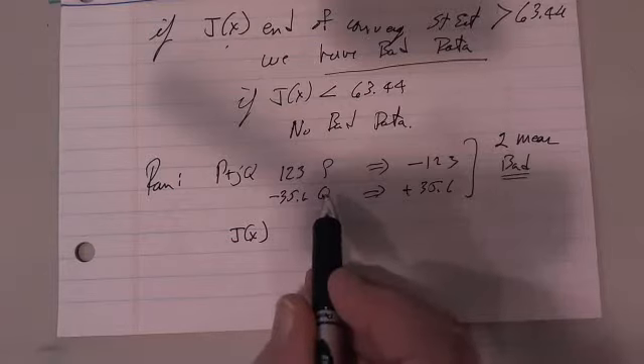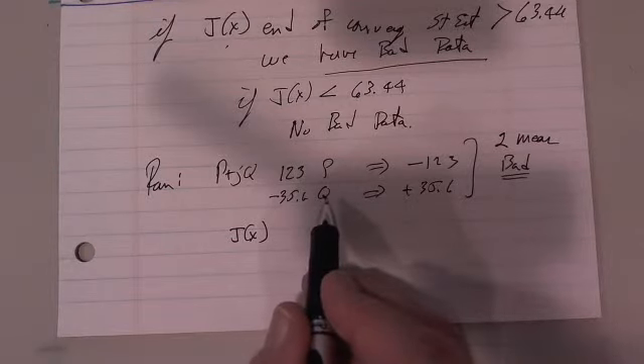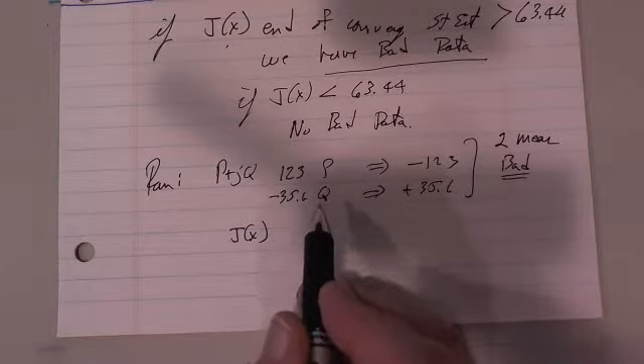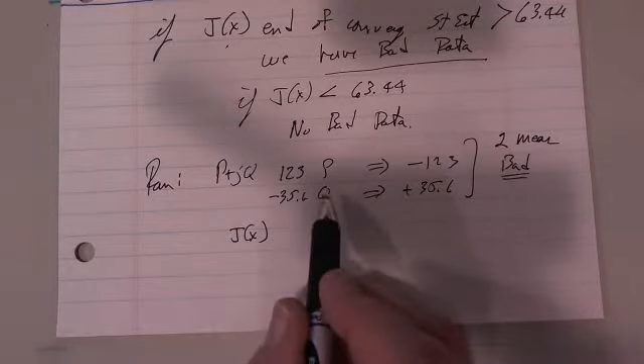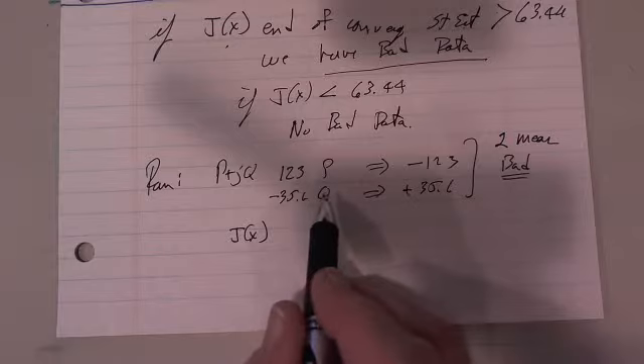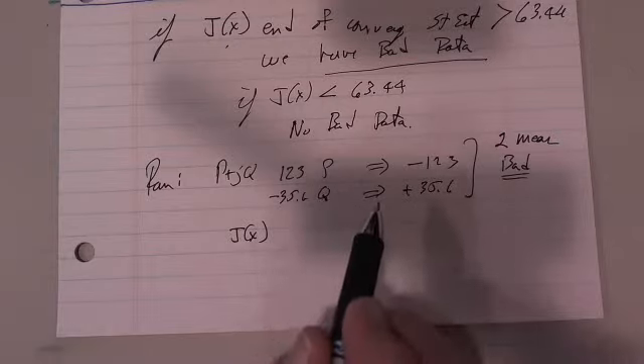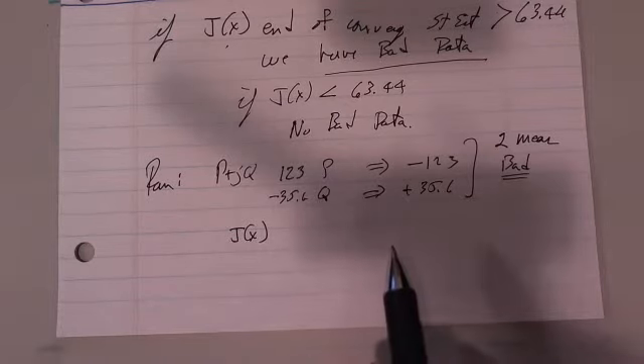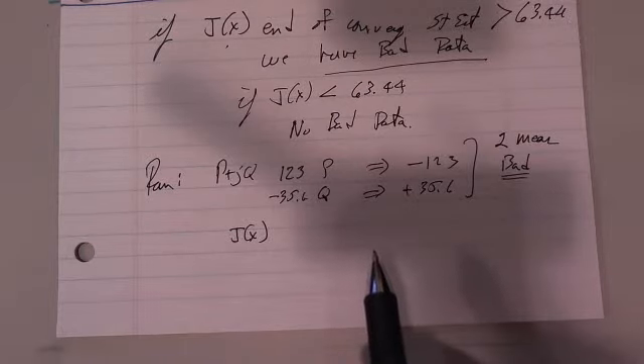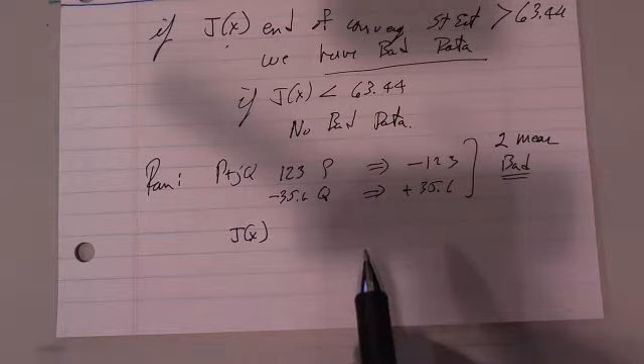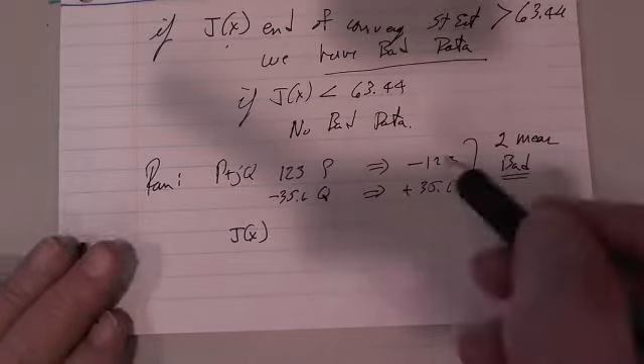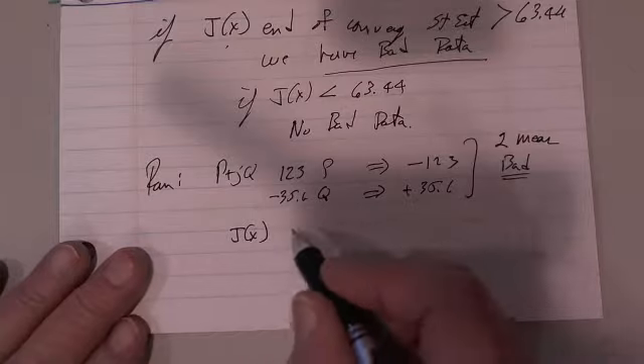A P and Q measurement requires that we be measuring voltage and current. If the current measurement, for example, is off, both the P and Q values will be bad. That's why you basically lose two measurements when one of them is bad — the other one will usually be bad too.